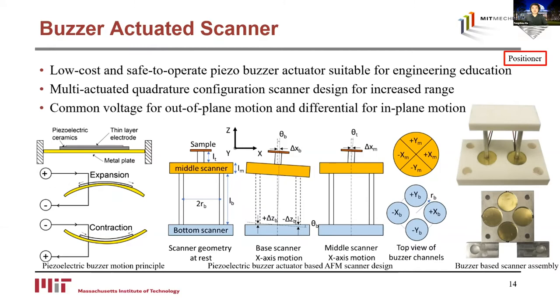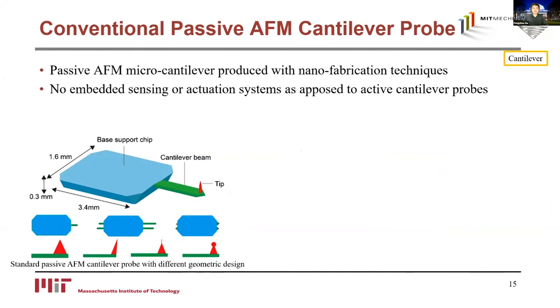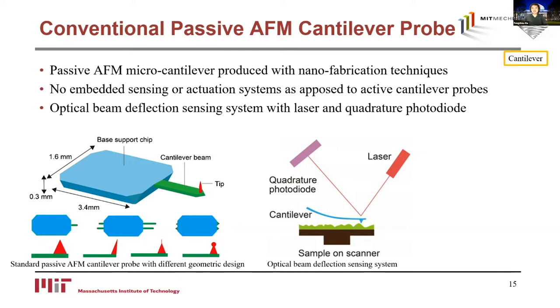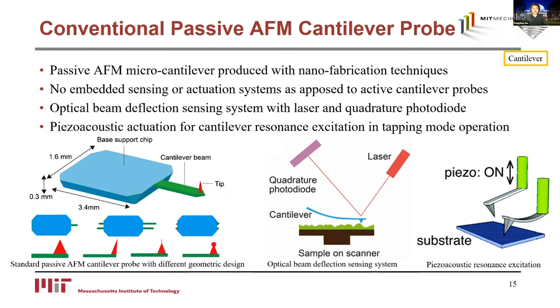Now let's take a look at the cantilever probes. Conventional AFM systems use passive cantilever probes produced with nanofabrication techniques. The probe is composed of a base support chip, a cantilever beam, and the probe tip. Multiple cantilevers and various chip geometries can be produced for different applications. To measure cantilever deflection, an optical beam deflection system is typically used — a laser is shined on the reflective coating surface of the cantilever and reflected onto a photodiode, allowing nanoscale resolution measurement. However, a transparent path for the laser is required. For dynamic mode operation, piezo actuators in the cantilever probe holder acoustically excite the cantilever resonance, but accurate control of the cantilever deflection is not possible in opaque liquid environments.